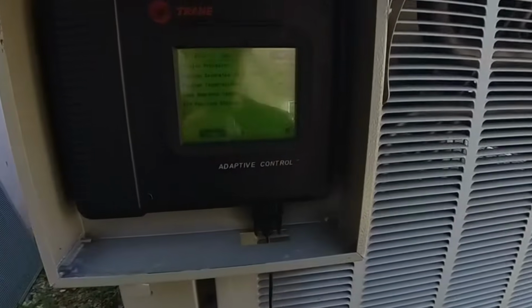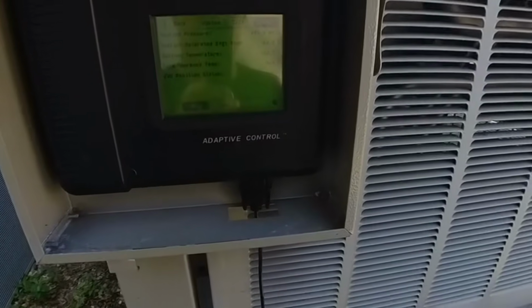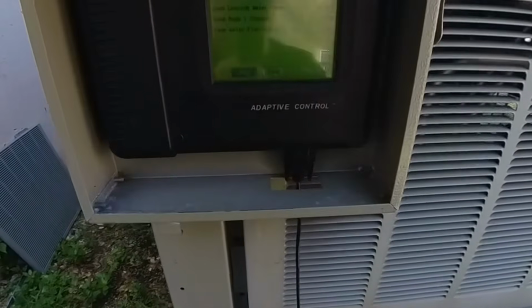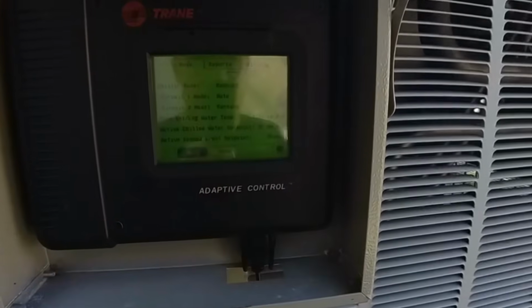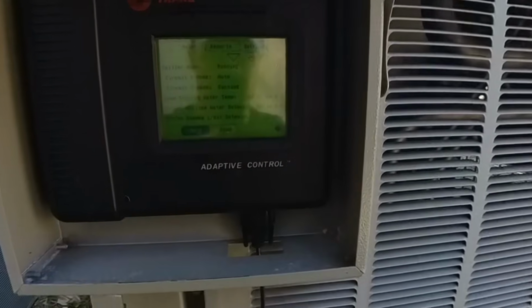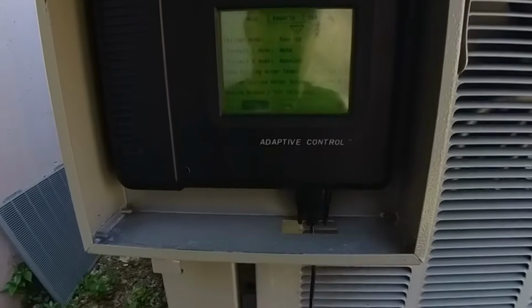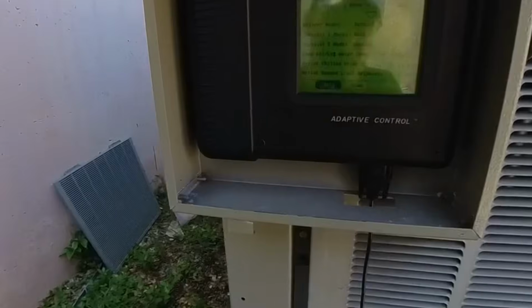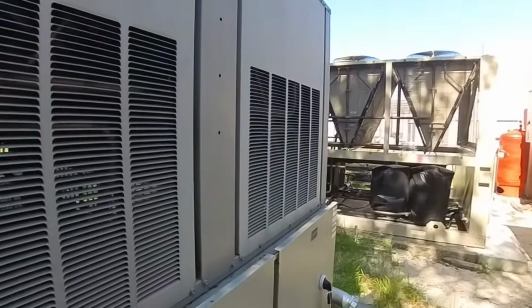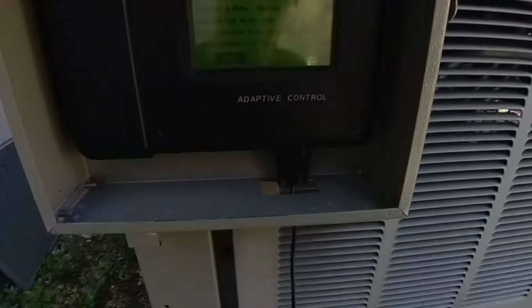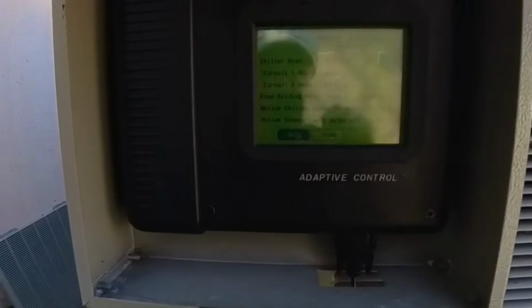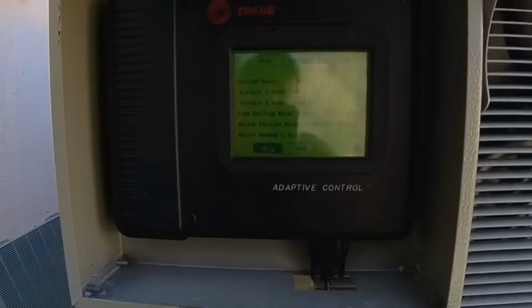Circuit 2 and reading on the CH530. Temperatures look better. Should stay online. Our water temperature got up to 64.7 entering. And this is the only chiller right now for the building. They have construction going on. There is another chiller over here. It's a Daikin. Know nothing about that one yet, and yeah, so that's what we're dealing with. Alright, let this run a little bit and come back to it and see if that other issue was there for the other circuit.